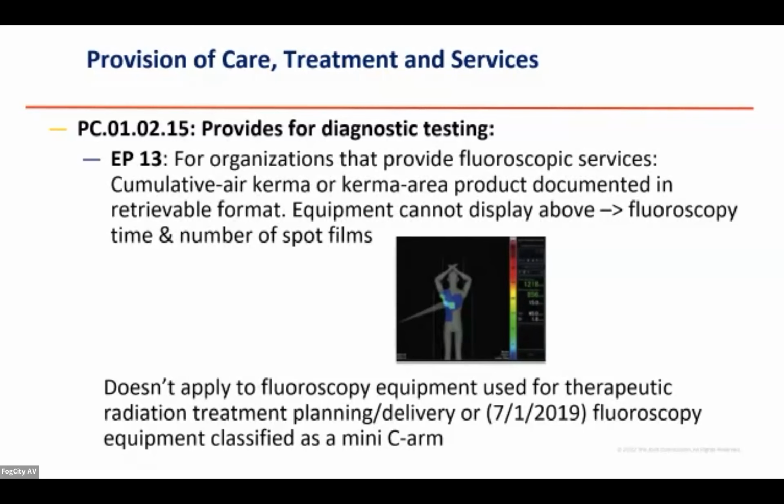And if you don't have a fluoro unit that does that, and by the way, that's standard on fluoro units since 2006, so let's hope you have a unit that does it. But in the event you don't, we ask that the fluoroscopy time, the beam on time, and the number of spot films taken is recorded in a retrievable format.